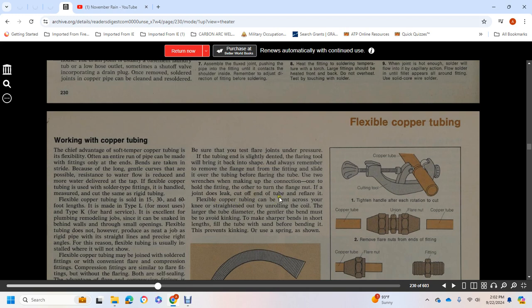Flexible copper tubing can be bent across the knee, straightened out, and the coil unrolled. The larger the tube diameter, the gentler the bend must be to avoid kinking. To make sharper bends in short lengths, fill the tube with sand before bending it to prevent kinks, or use a spring as shown.